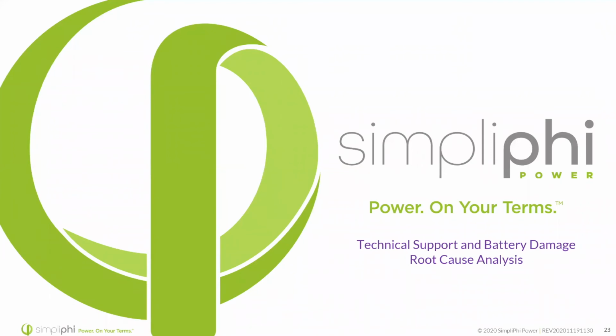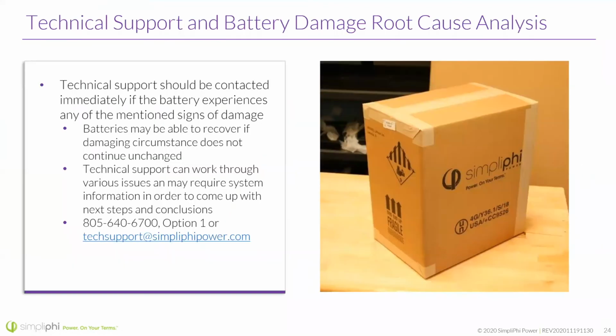So talking about technical support and battery damage root cause analysis, technical support should always be contacted immediately if the battery experiences any of the mentioned signs of damage. So that could be if the BMS opens or the circuit breaker goes off. Those are things, reach out to us right away, because oftentimes the battery may be able to recover if damaging circumstances do not continue unchanged. Basically, if we could find the situation and fix it from the get-go, oftentimes it won't cause bigger damage down the road.